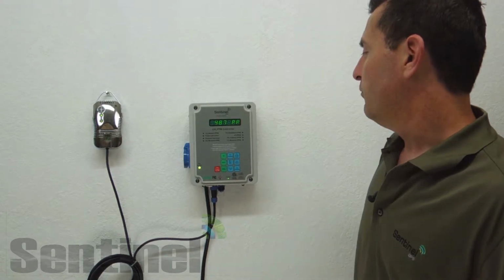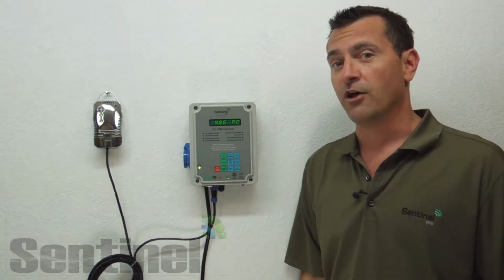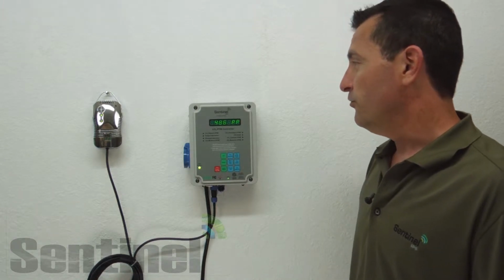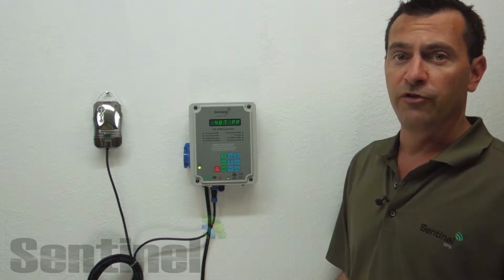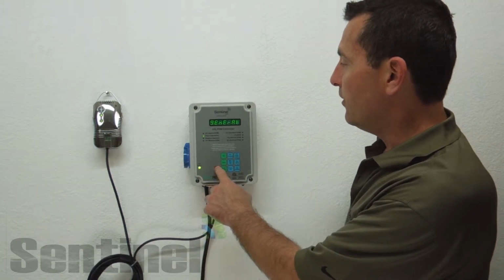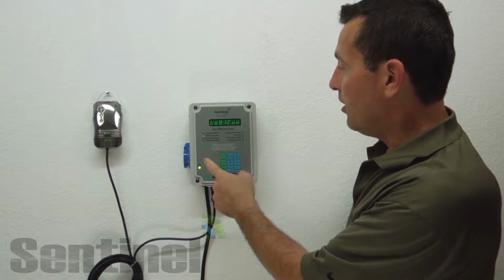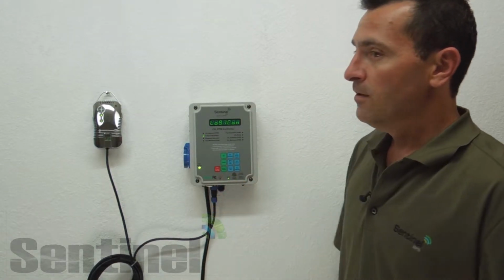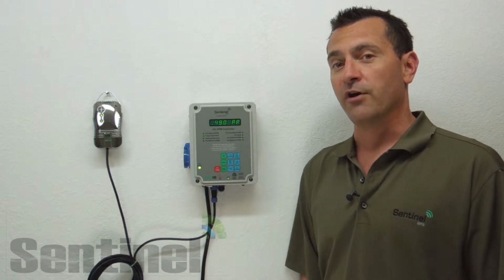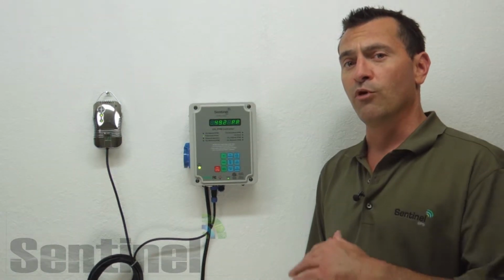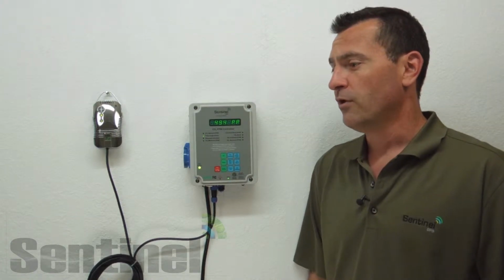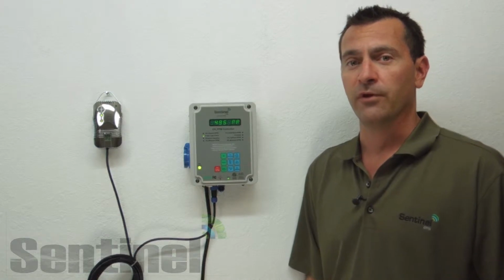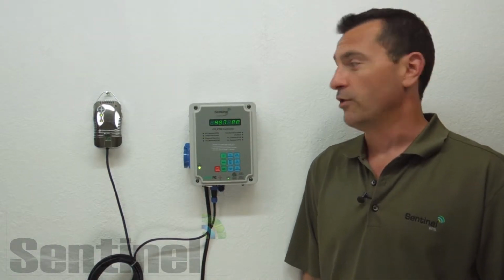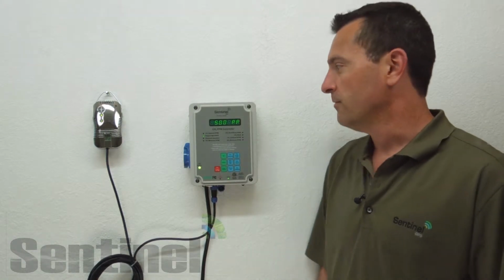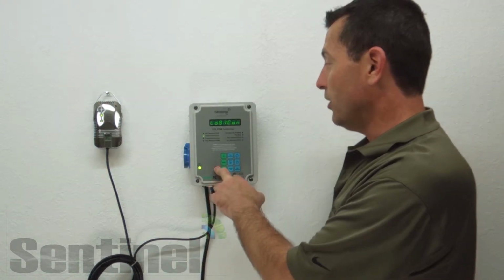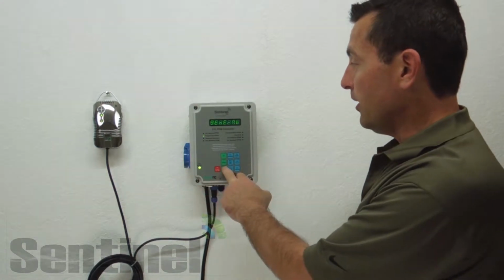You'll notice we have a green LED up here that's giving you a constant updated reading of your CO2 levels in your room. To set the unit up, first you need to decide if you want to use the fuzzy logic mode or the CO2 generate mode. If you're using a compressed CO2 bottle and a CO2 regulator, you'd want to set this up in the CO2 fuzzy mode. So you press the CO2 fuzzy on off, switch it to logic on, and press enter. What that does is it more rapidly turns your valve on and off and maintains a more level CO2 level inside your growing space. But that rapid turning on and off would not be good for a CO2 generator running off propane or natural gas where you're turning a flame on and off consistently. If you are using the CO2 generator, you would switch this back to generate, press enter.